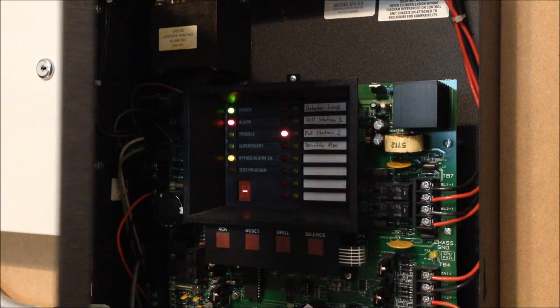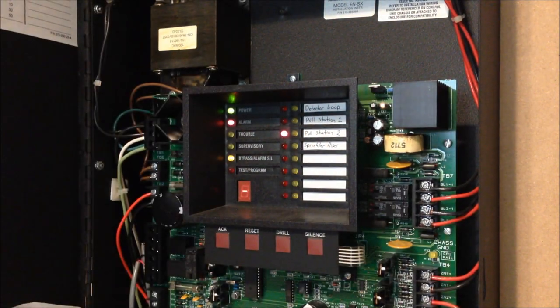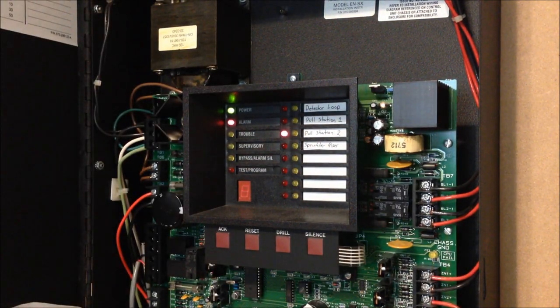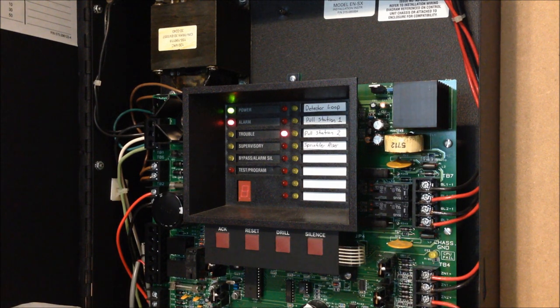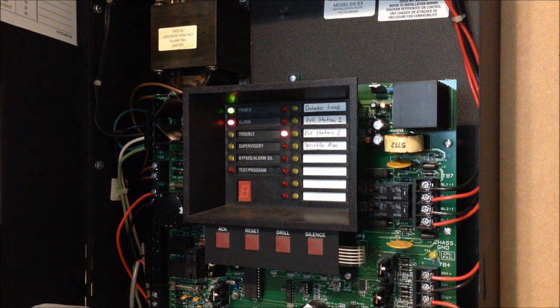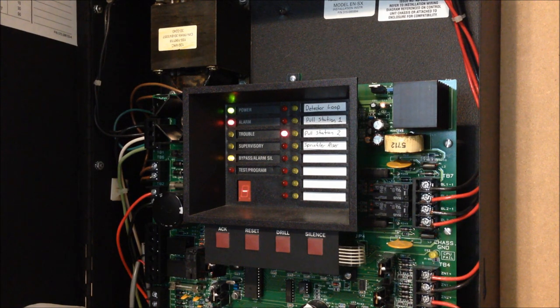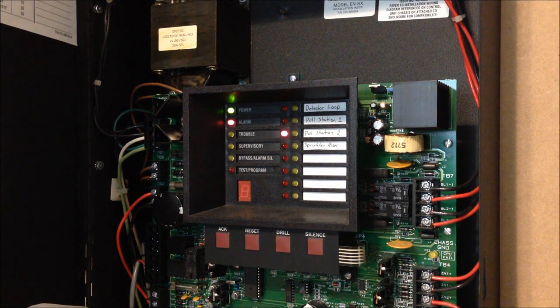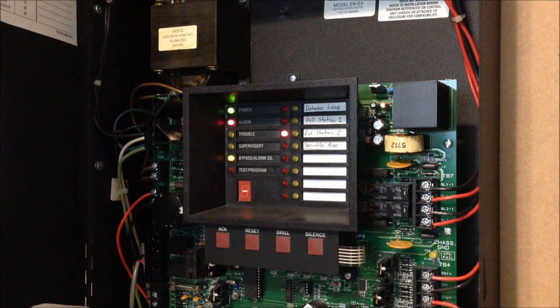Oh wait, never mind, there it goes. I thought for a second that I had accidentally left the Federal Signal's NAC on non-silenceable, because I heard the L-Series cut out really quickly. But I forgot that since it's doing code three, it was going to finish the code three round before silencing anyways.